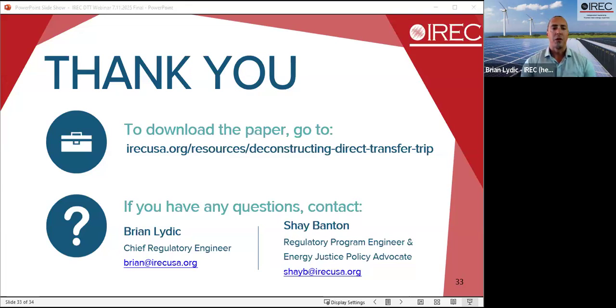Yeah, I don't know if anybody else wants to weigh in here, but my answer to that would be that they are inverter-based DERs themselves and have the same types of anti-islanding protections that are required of other inverter-based DERs. So they're going to be UL 1741 SB certified. They're going to have to follow all of the IEEE 1547 requirements. And so basically all of the things related to islanding algorithms and whatnot that apply to energy storage based inverters as well.